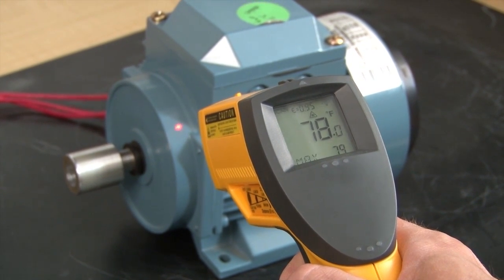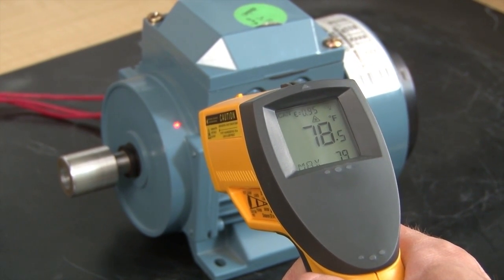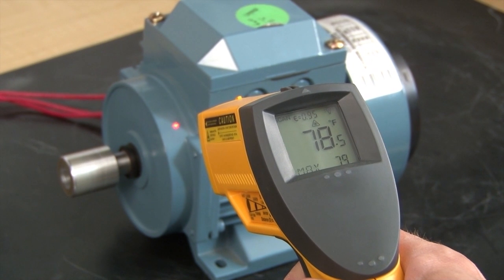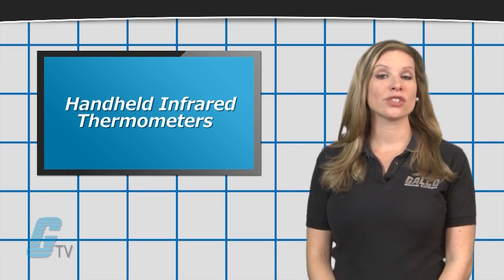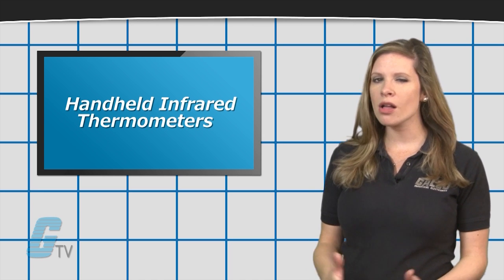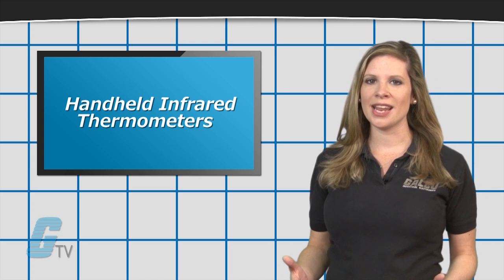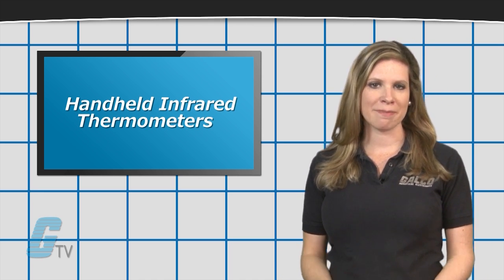The non-contact nature of IR thermometers allows you to take measurements without actually touching the product being measured. This allows for additional safety for the worker while also limiting possible contamination to the product.